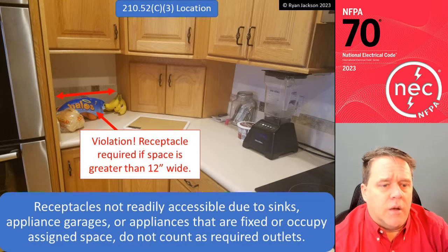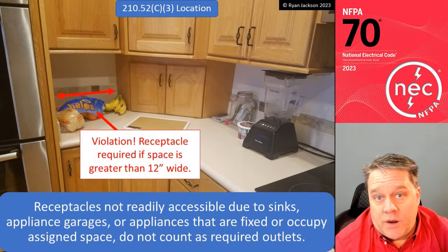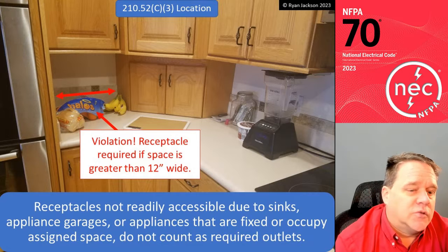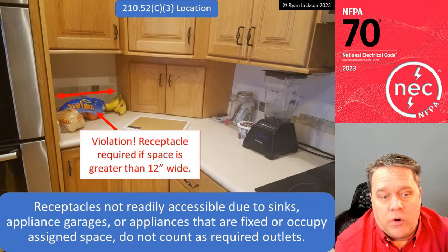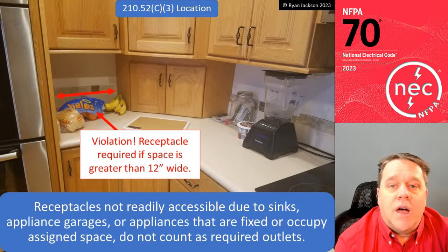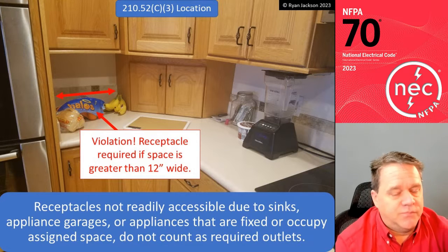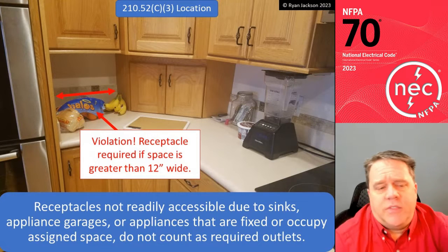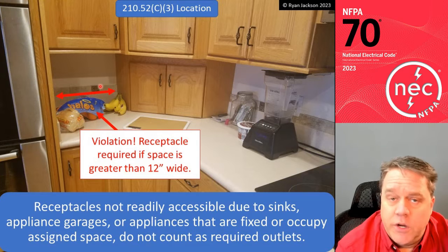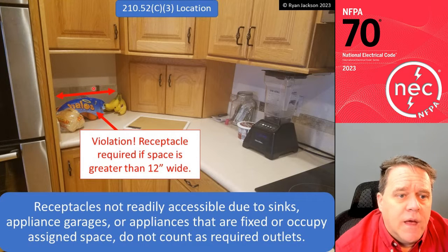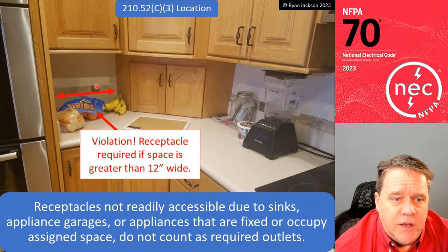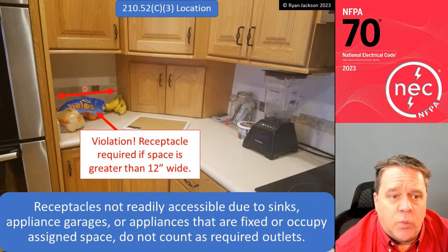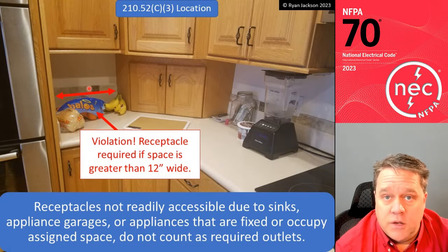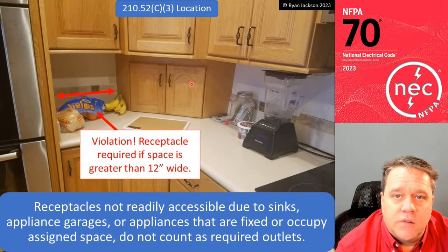210.52(C)(3), just about done. Receptacles not readily accessible due to sinks, appliance garages, or appliances that are fixed or occupy assigned space do not count as required outlets. All right. Here in the picture, I think we're missing a receptacle outlet over here on the left. So this is counter space. It is 12 inches wide or bigger. Therefore, it needs receptacles. And the space consumed by appliance garages like this does not count as countertop space.